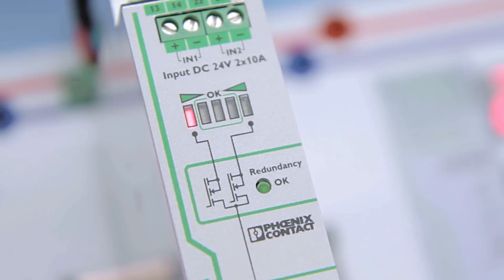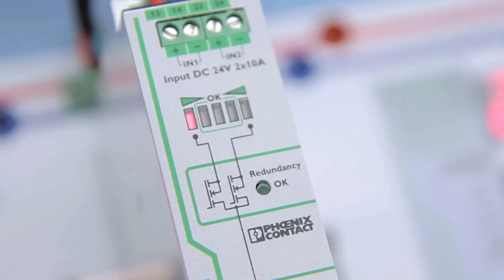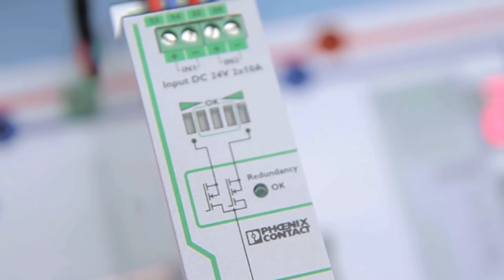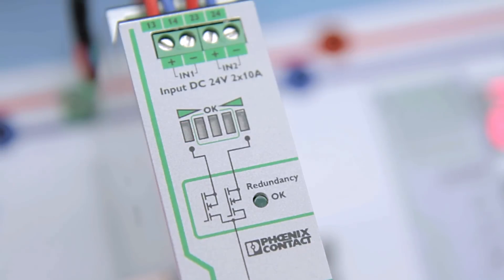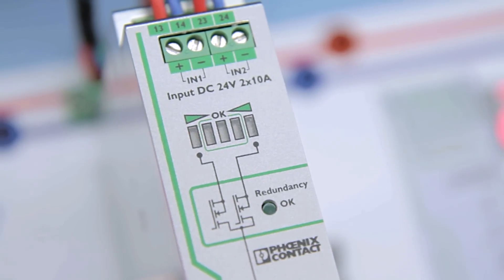Normally, if the load starts drawing more current than one power supply can provide, the redundancy would be defeated. But O-Ring avoids that problem. When the load draws more current than a single supply can provide, a redundancy OK alarm is sent to the control system, and the redundancy OK LED will blink.